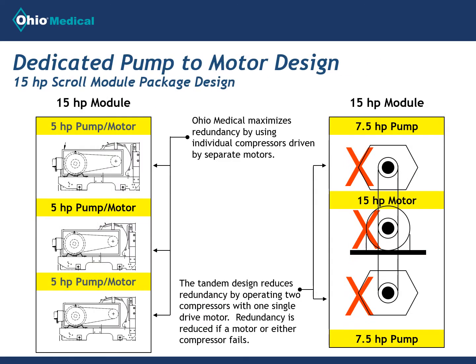Ohio Medical's scroll systems are designed with dedicated motors for each compressor. This provides more redundancy in the event of a motor or compressor failure. In the example shown, Ohio Medical's 15 horsepower is achieved by using three 5-horsepower motors and compressors versus two 7.5 horsepower compressors driven by a single 15 horsepower motor.